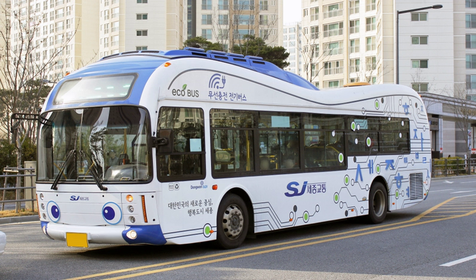The ferrite cores in the primary coils were changed to a U-shape, and the cores in the secondary coil were changed to a flat board shape to pick up as much flux as possible. This design allows the vertical misalignment to be about 20 cm with 50% power efficiency.